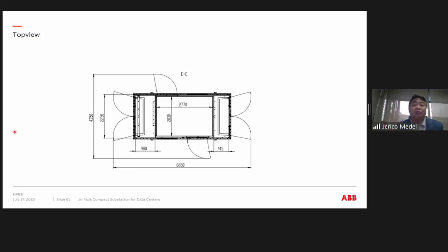And the type testing is actually for that purpose. That's why you'll notice non-type tested equipment will have a bigger footprint, much bulkier compared to type tested equipment. The type tested equipment is conducted to actually prove that the creepage distance provided inside the switchgear is compliant and can withstand the conditions required in the type testing parameters. So I think that should address your concerns, sir, if you're doing audits. Perhaps if you have type tested equipment, you can check where the type testing certificates are.